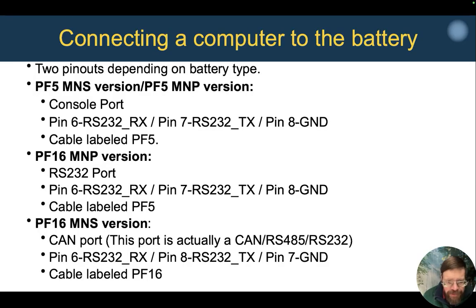For the PowerFlow 16s, there's two different versions. The newer ones have an RS-232 port and use that same cable labeled PowerFlow 5 on the adapter. The older Midnite Solar branded versions, and some earlier Midnite Power branded versions, only have 3 ports—a combo port with everything in the same port, since none of them use all 8 pins of the RJ45. On those, the CAN port is the one you'll plug into, and it's a different pinout, so it has a different cable labeled PowerFlow 16.